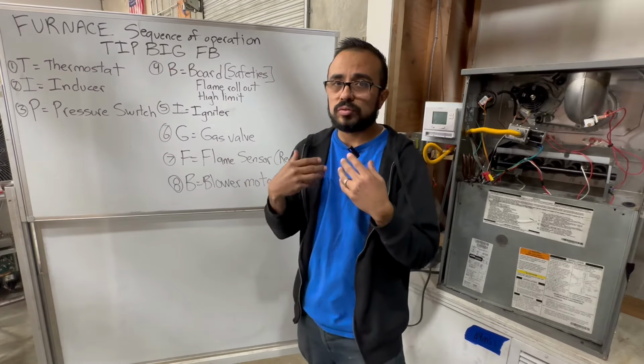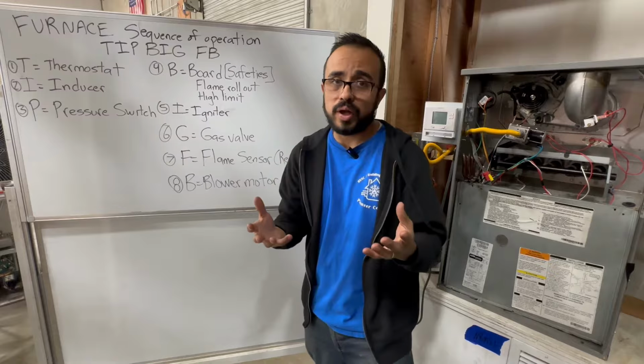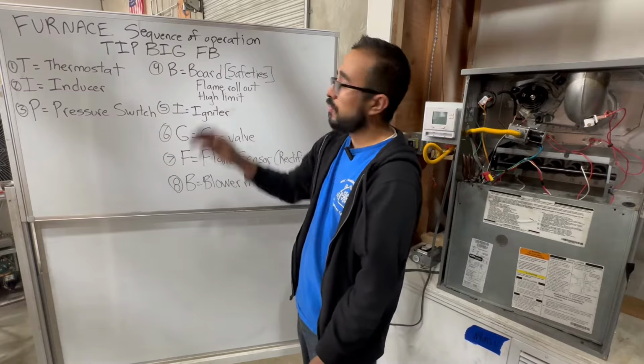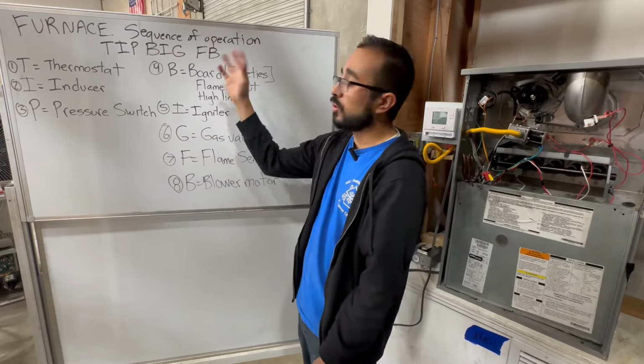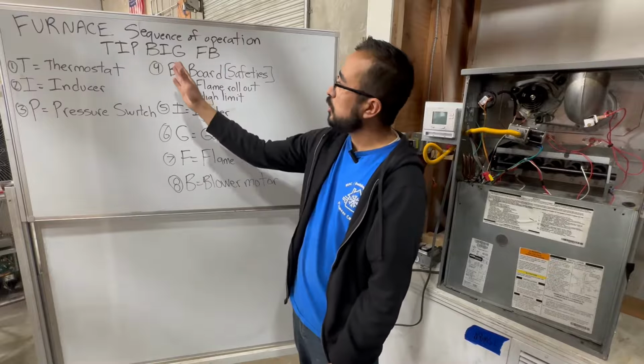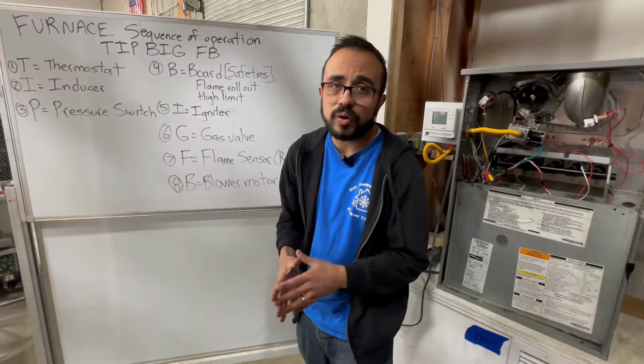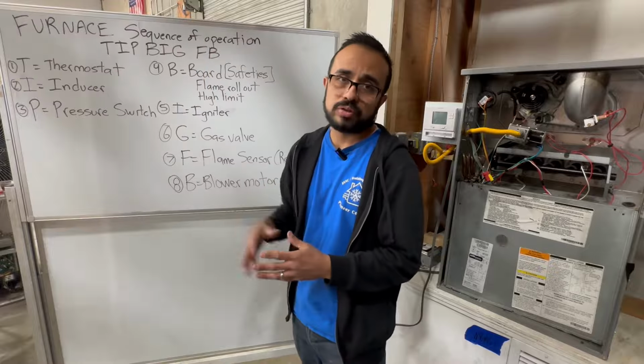And the way that I like to approach the acronym, the TIP Big FB, let's say in the I, which is your igniter, let's say it doesn't turn cherry red. Are you going to check for flame rectification, are you going to check your blower motor? No, you're going to check if your board is sending out 120 volts. You're going to check backwards.